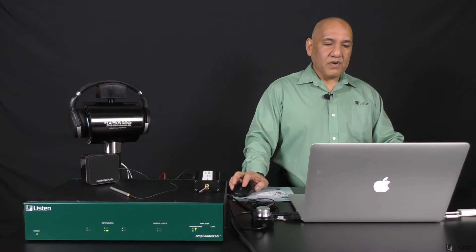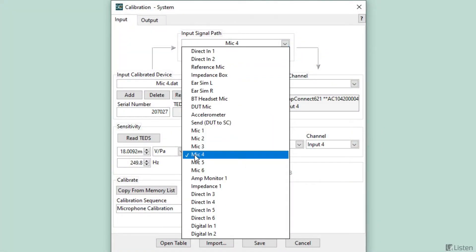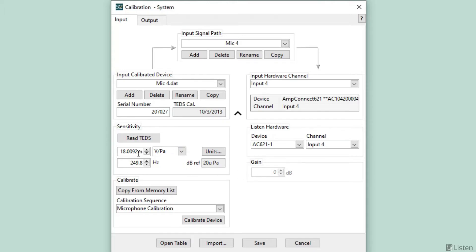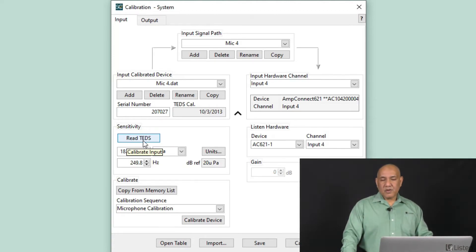Another nice thing about the 621 is that we have integrated full TEDS support. So if you have a TEDS microphone, this quarter-inch microphone is a TEDS-compatible microphone. And if I select the input, which is input four here, you'll actually see I can click this button to read the TEDS data off. The TEDS data will return the serial number as well as the internal calibration that's stored on this microphone. And there's the sensitivity as stored on that microphone. So that's fully integrated AmpConnect 621 support.